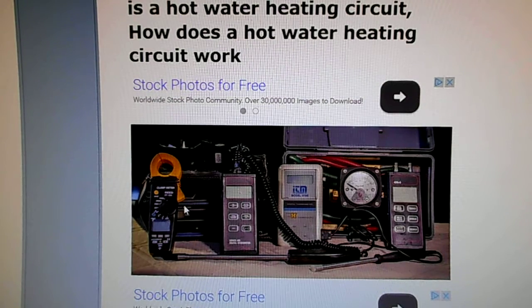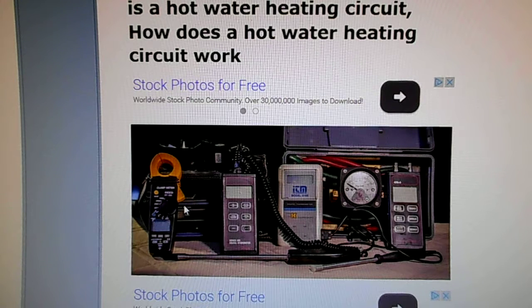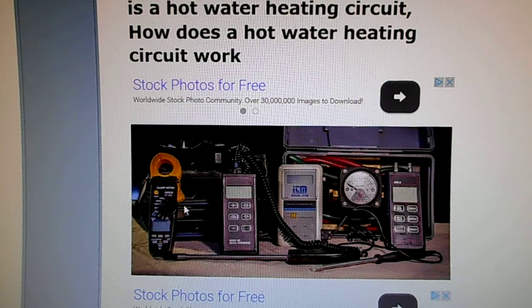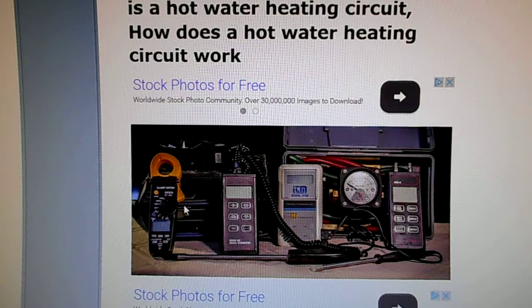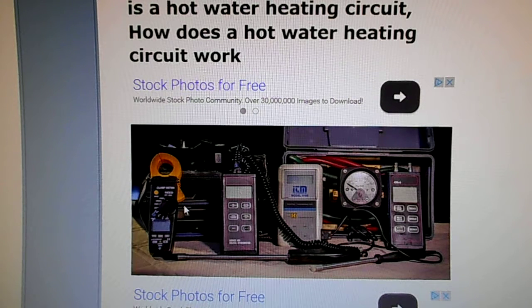Heating water chemical treatment: chemicals necessary to treat the heating water may be added manually or automatically. It is usually a manual function in most applications; however, on more sophisticated systems, water may be automatically tested and chemicals added automatically. The chemicals may be added to either the heating water supply or return line. It is suggested that chemical tests be performed on a weekly basis to determine chemical concentration, and that conditions be maintained as directed by a chemical treatment specialist. Chemical treatment is necessary to inhibit rust and corrosion of the water side of all heating water components.